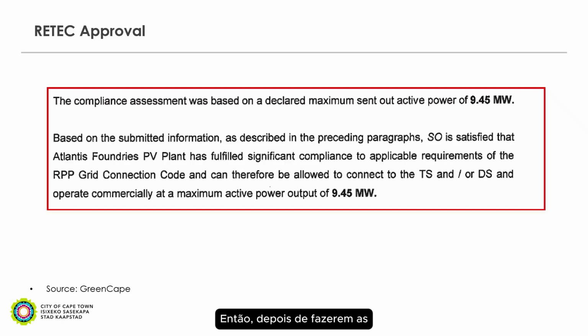And then after they have done their site inspections to verify those results, they typically provide an approval letter which basically indicates the following on the slide. The compliance assessment was based on the declared maximum active power. In this case, for this particular plant, it was 9.45 megawatts. And then they indicate, based on the submitted information, that the plant has met the requirements and is now deemed to operate commercially at that output power.